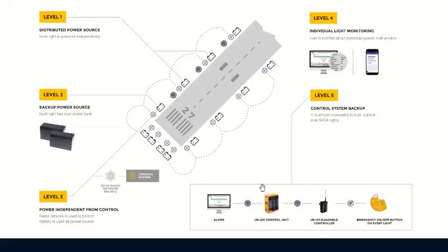Well, let's imagine for a moment that the software stopped operating. It's not something that cannot happen. It's software. It can be frozen. There can be some bug. Normally in airports that are using software from traditional lighting systems, the problem can be solved, but sometimes it requires weeks or months before your supplier will come to you and fix it. Until then, you have a problem with the control over your system. In our case, if ALCMS is not operating well, that's not a problem because you have a backup control panel that is always installed in the tower. You have physical traditional knobs that you can use to activate groups of lights and change their intensity.